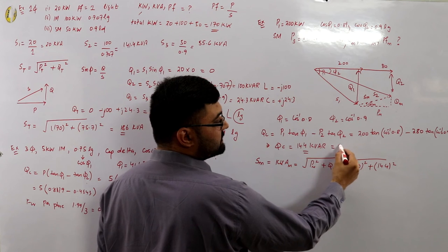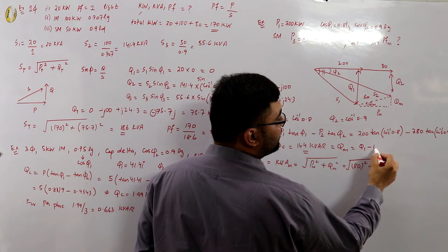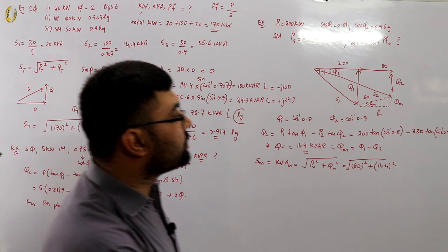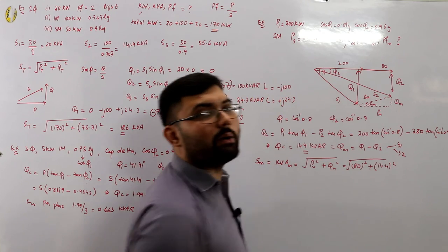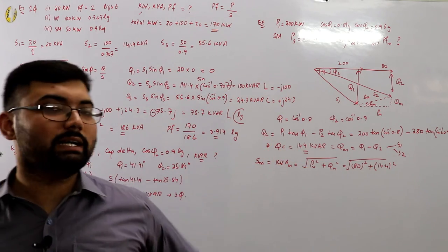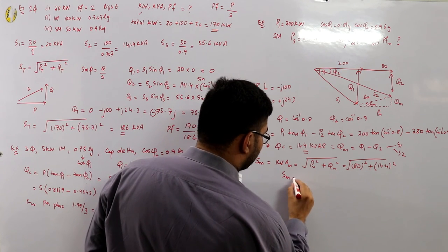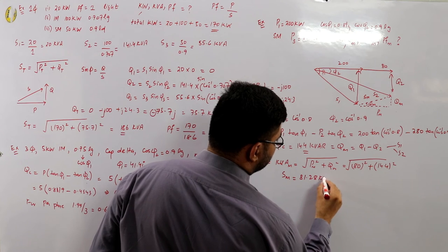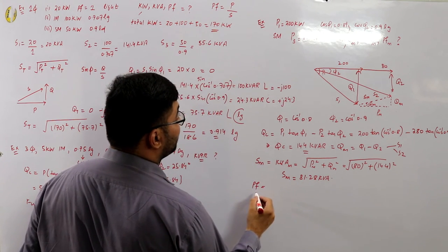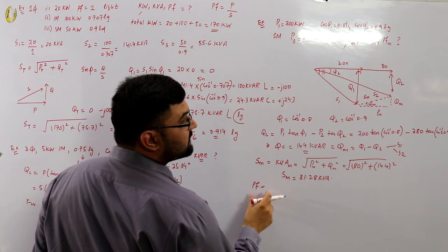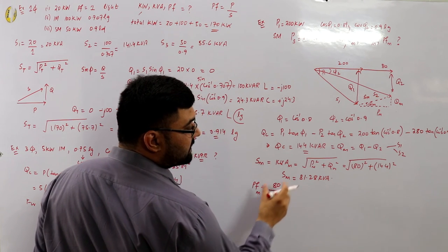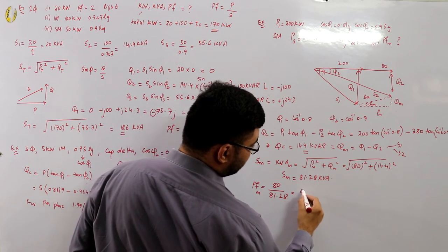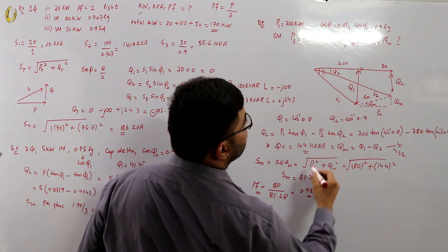S_M = √(80² + 14.4²) = 81.28 KVA. The power factor of the synchronous motor is P_M/S_M = 80/81.28 = 0.984 leading. This alternative approach directly uses the formula Qc = P₁·tan(φ₁) − P₂·tan(φ₂), which is more straightforward than the method used in the previous video.